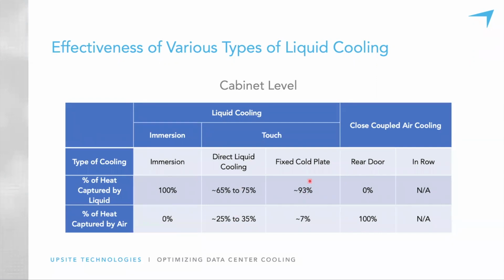The fixed cold plate solution picks up 93% of the heat, approximately, and this is the result of an independent study done by NREL, leaving 7% of the heat to be dissipated by other means. This is such a small percentage that in a fixed cold plate solution, no fans are necessary. So the liquid is picking up the bulk of the heat, and the rest of the heat just convectively or conductively goes out through the cabinet and is picked up by the ambient air. So no fans are required for this solution. In many of the direct contact liquid cooling solutions, fans are required, but they're running at a very low speed, so they've really benefited from the fan affinity law, and they're using a very small fraction of the energy that was used when they were a full air-cooled solution.